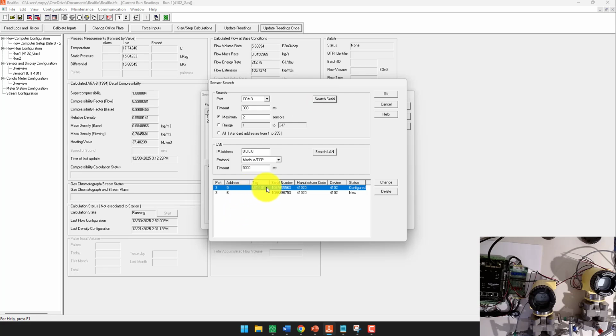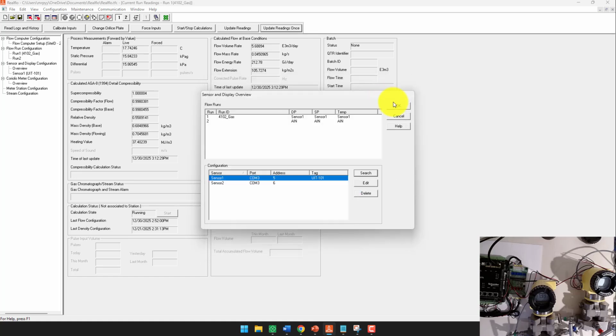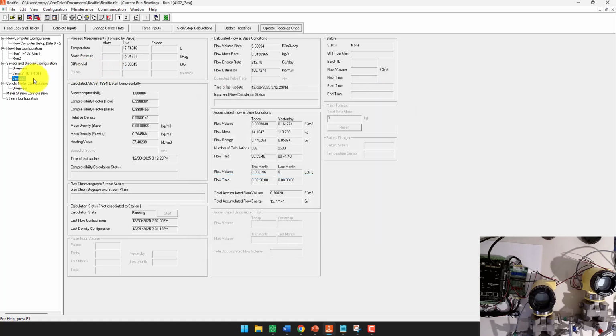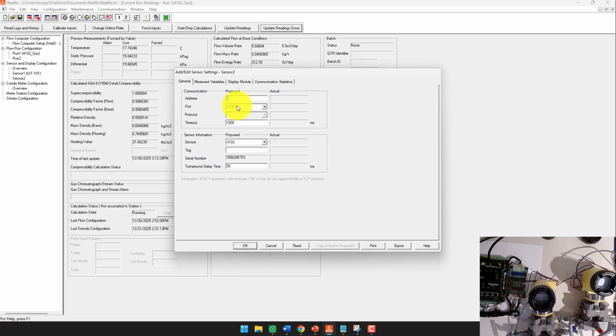So we found UIT 101, which is the first one we have set up, and then this is the second one. Typically this would be address 99, but in this situation I've already changed the address, so it's coming up as 6. So we go ahead and hit OK and OK. So now we see sensor 2 here. The address is 6, which is all good. We want to change our tag so it identifies as a different tag from the previous one. Everything's all set up, looking good.